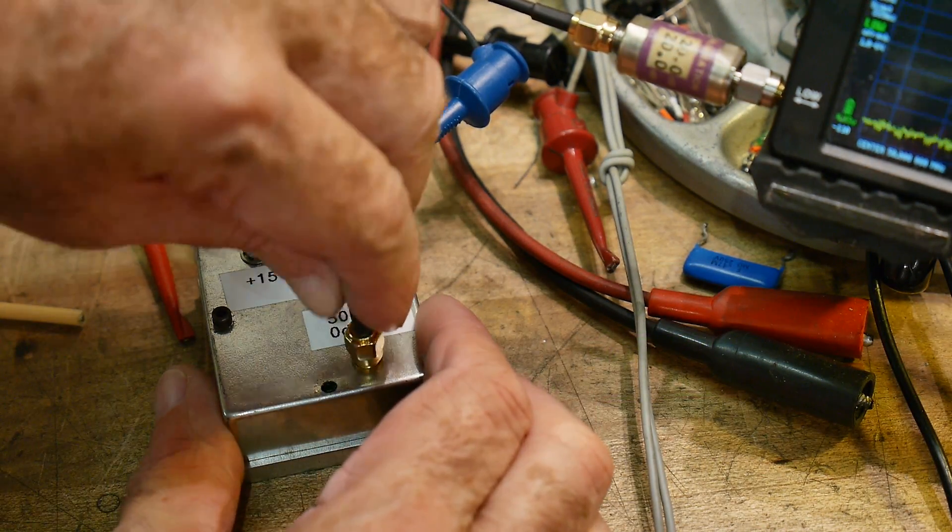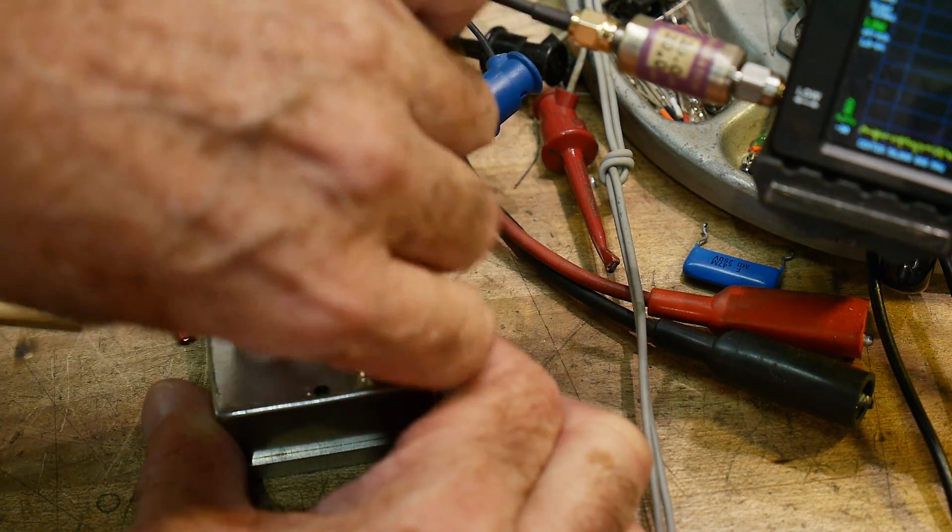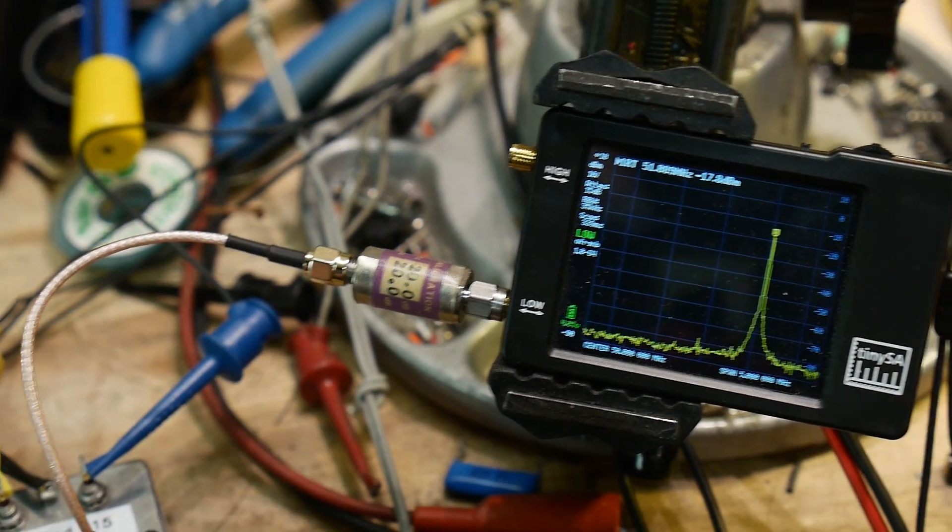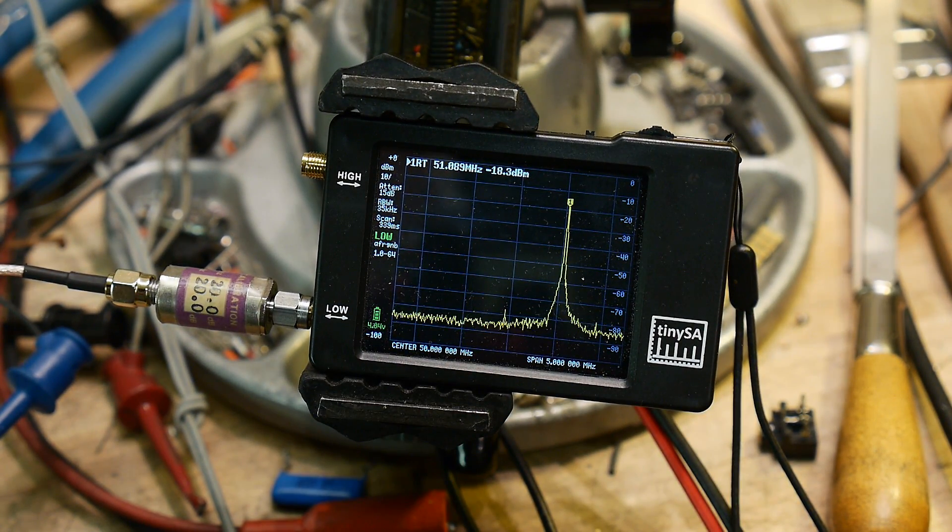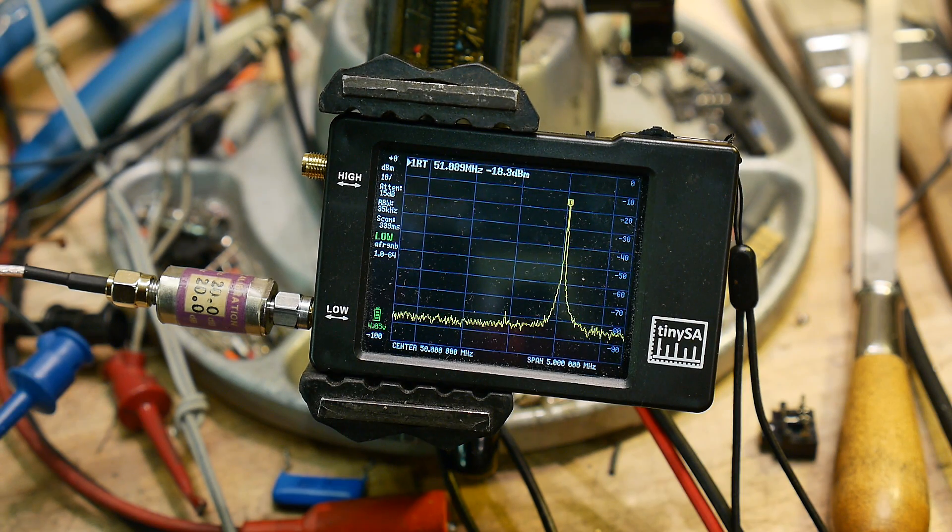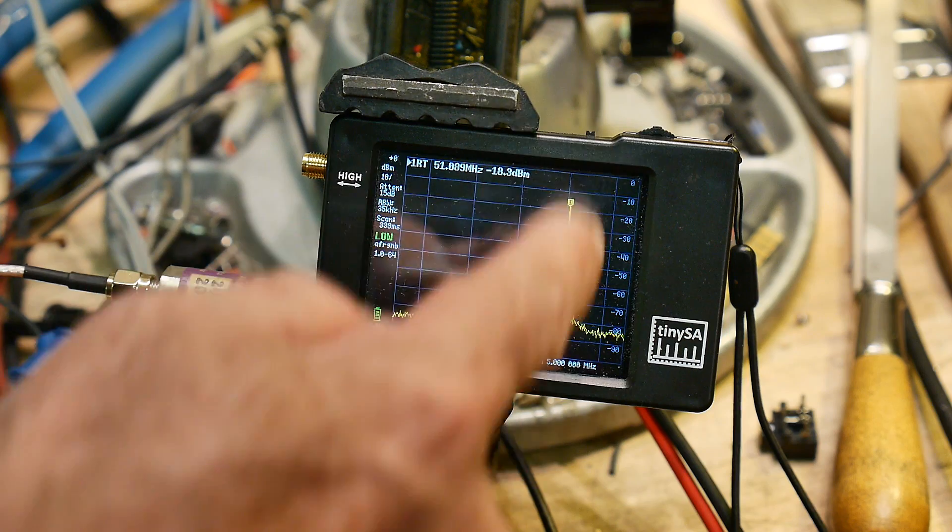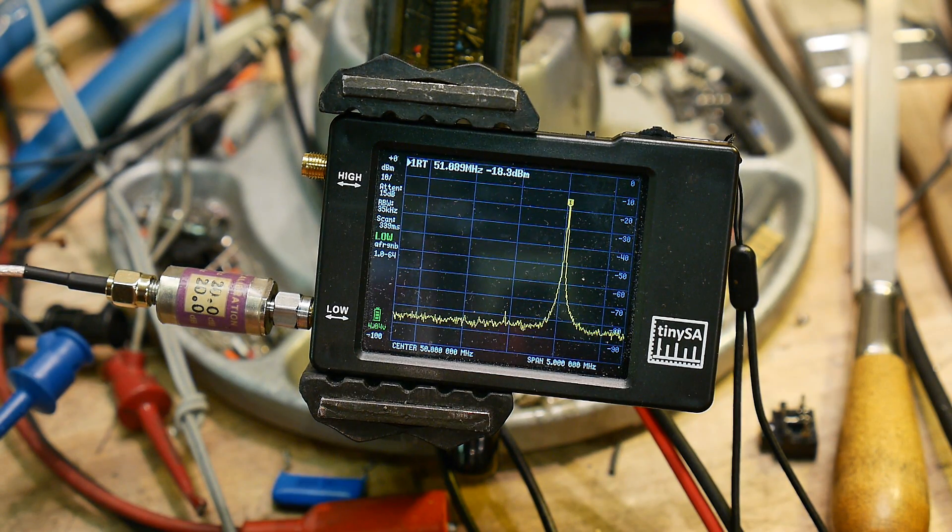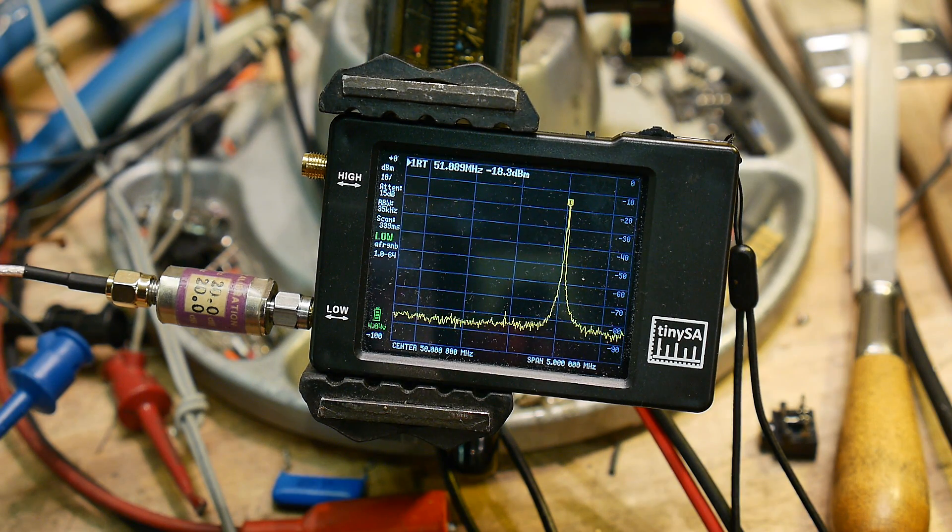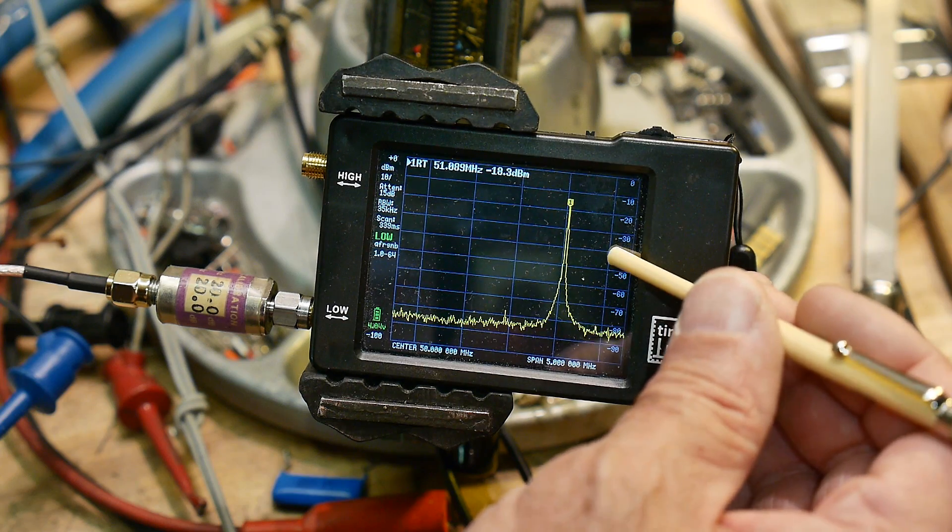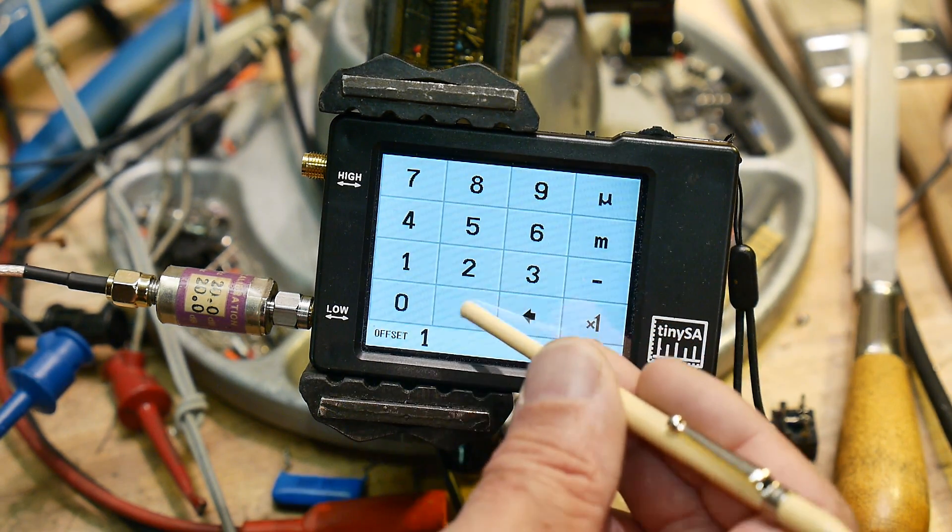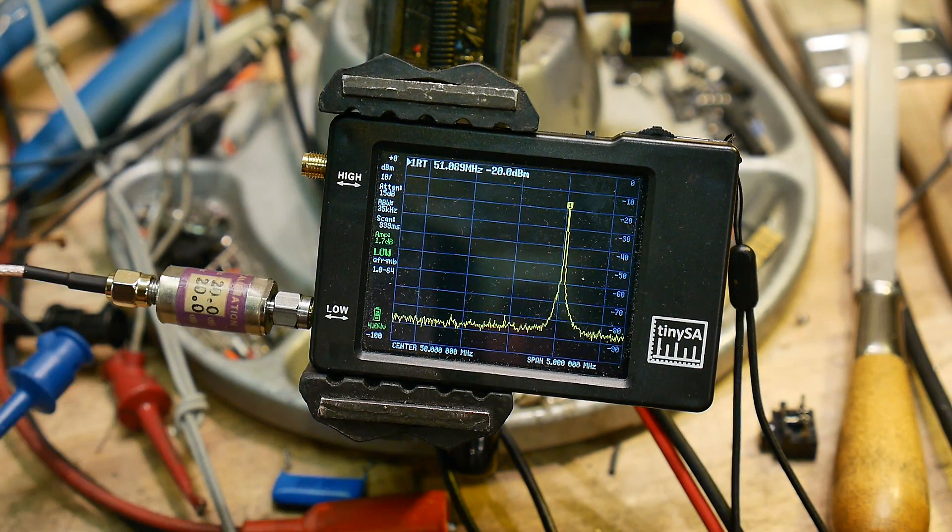All right, so let's hook up the calibrator. And I have the calibrator going into a 20 dB pad into the spectrum analyzer, and we're measuring minus 18.3. So it's fluctuating a little bit, but minus 18.3. And there you can see our 50 MHz carrier. So it is a bit off. We are about 1.7 dB off. So if we go to level external amp, and we put in 1.7, now we're measuring minus 20 dBm exactly.